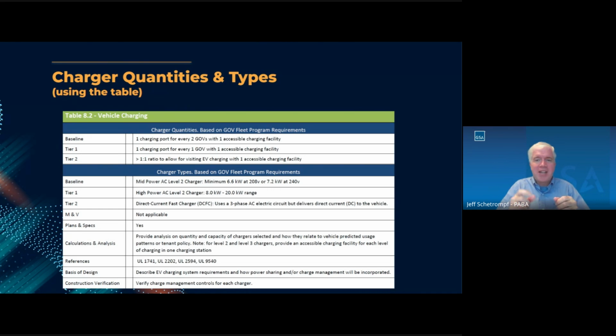kW. It's important to note that as the kW values go up, so does the demand on the electrical infrastructure, which a given facility may or may not be able to fully support. Larger installations or higher kW values may well lead to significant electrical upgrades or new utility fees coming into that site.